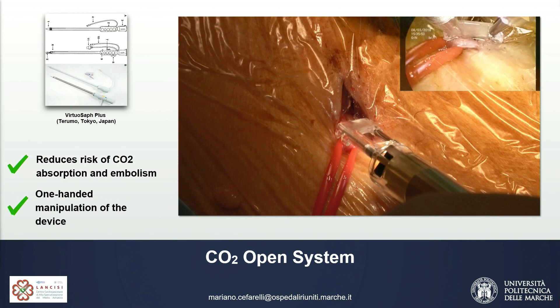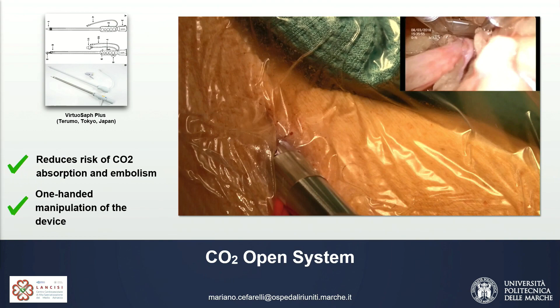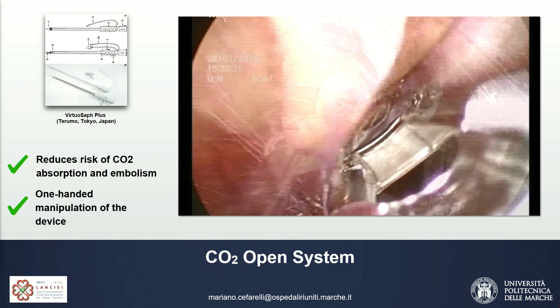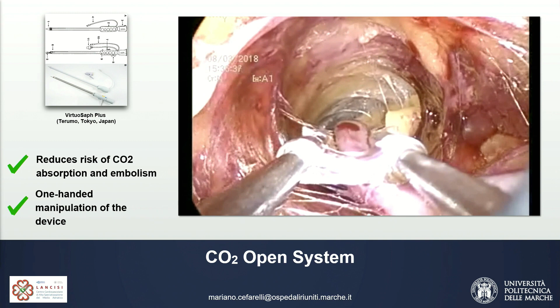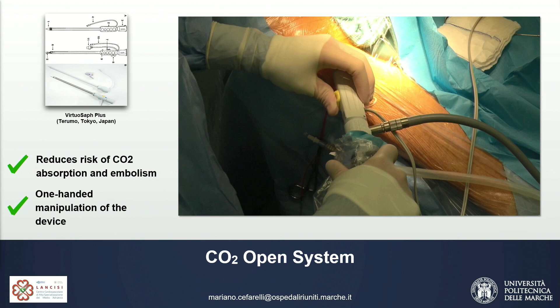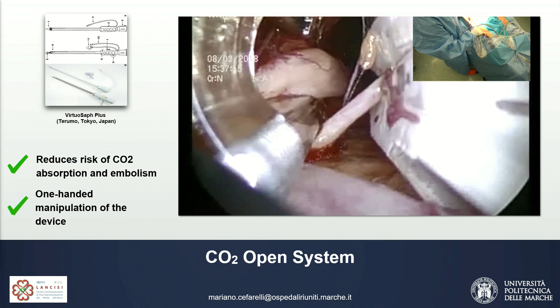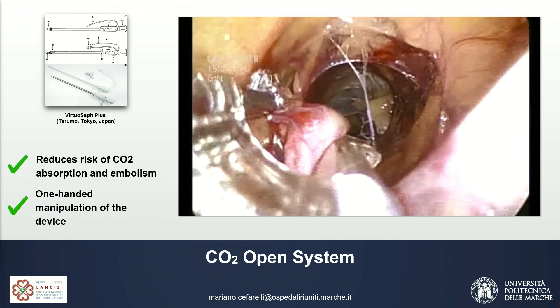The dissector is then pulled out and the endoscope and CO2 are connected to the harvester. So the device is then advanced through the tunnel until it reaches the proximal end. The V-lock is then opened in order to hook and protect the vessel. And pulling back on the harvester, it is possible to feel some resistance due to the presence of a side branch. So as you can see, it is possible to use the device with only one hand. And the collateral is then gripped and cauterized with cautery operated using the foot switch.